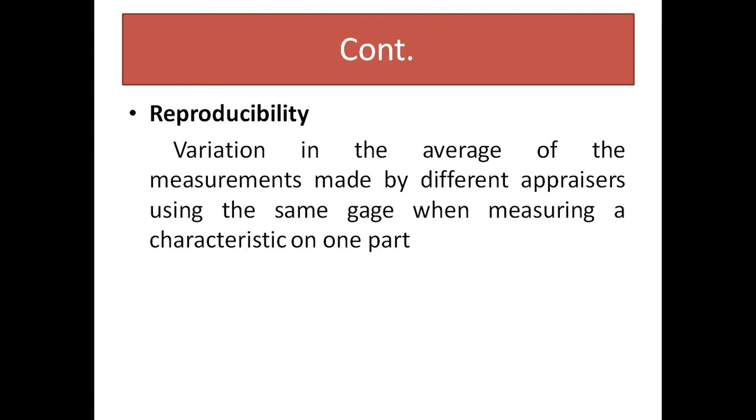Last is reproducibility, which is the variation in the average of measurements made by different appraisers using the same gauge when measuring the characteristic on one part. Different operators will measure the same part with the same instrument. The difference is: in repeatability, the same operator measures the same part with the same instrument, while in reproducibility, different operators measure the same part with the same instrument.